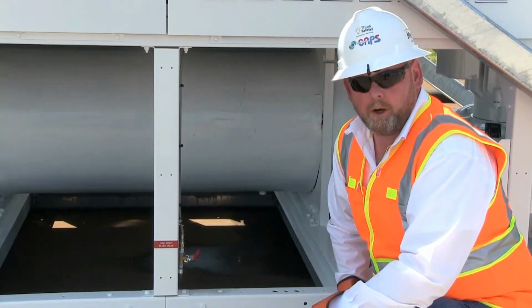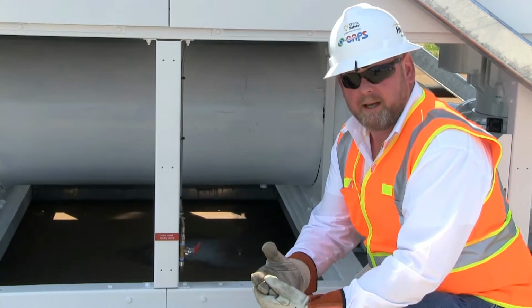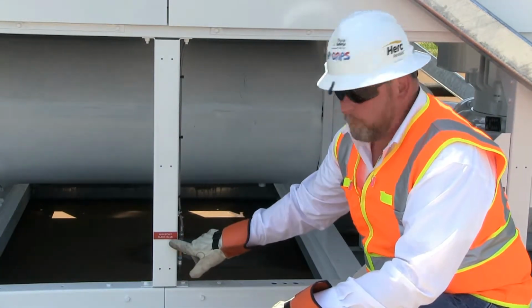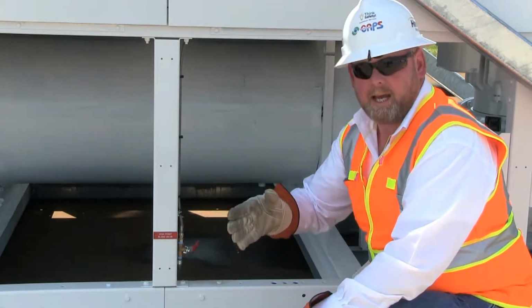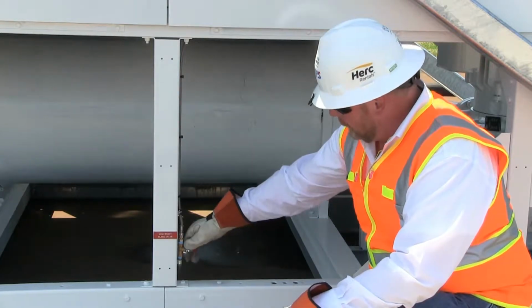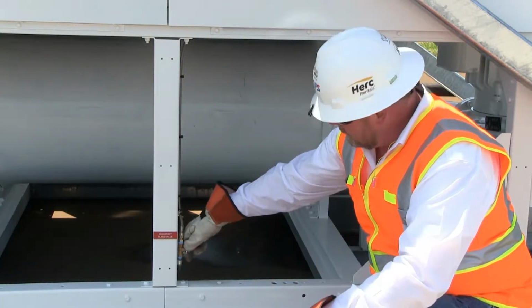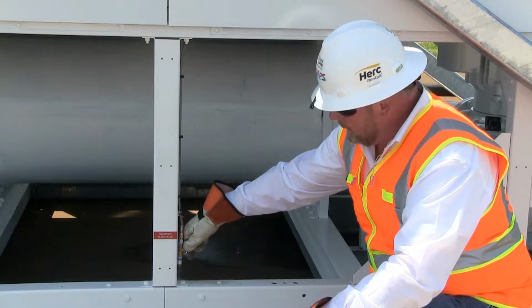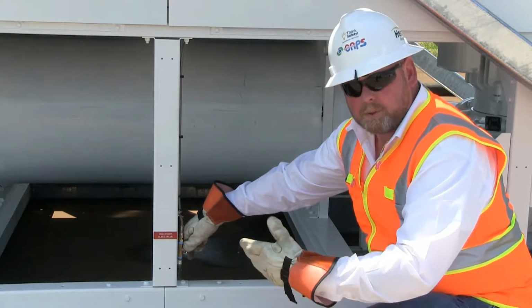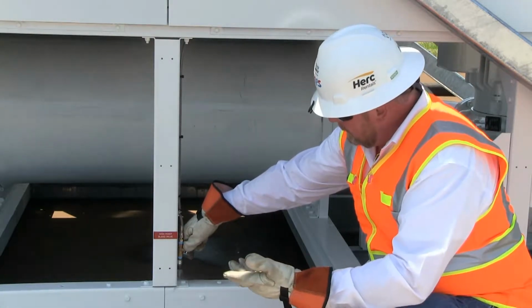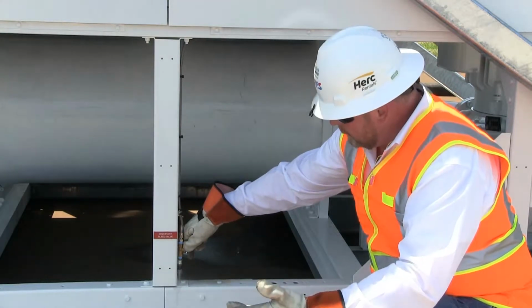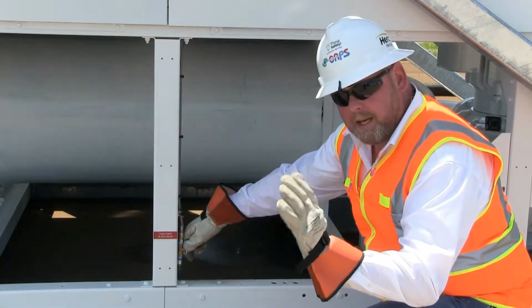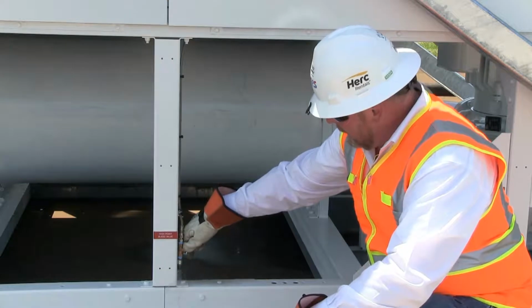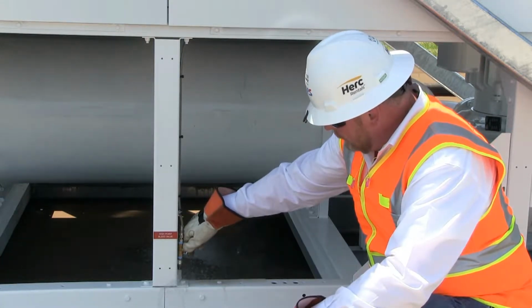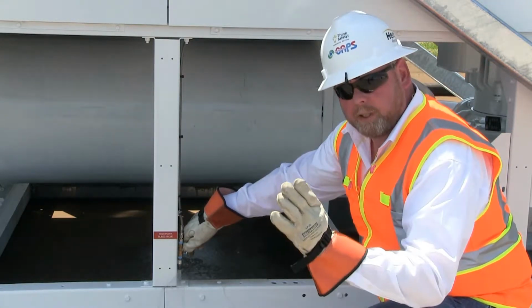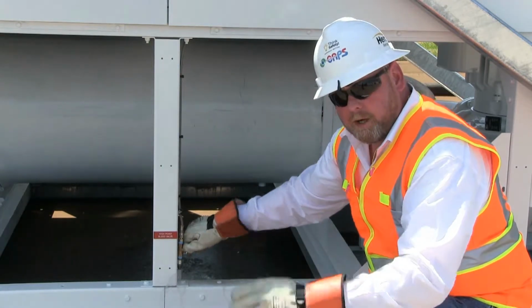Okay, we've cycled our pump several times as we filled it up. And this is clearly labeled high point bleed. It's on the opposite side of the fill line. If you open this valve here, it's plumbed to the top of the heat exchanger, and you'll hear immediately that we have air there. I'm demonstrating that as the water's going in, the air pushes out. After just a few seconds, you'll see we had just a little bit of air left in there, but now we've got a full stream of water coming out. Once we get completely full flowing water, all of our air is out of the system.